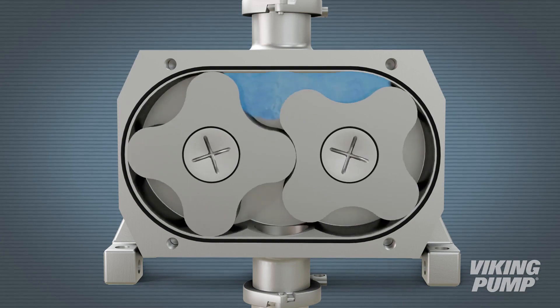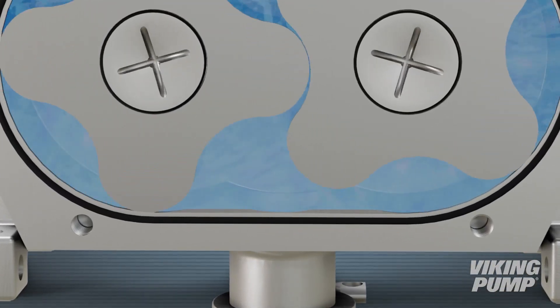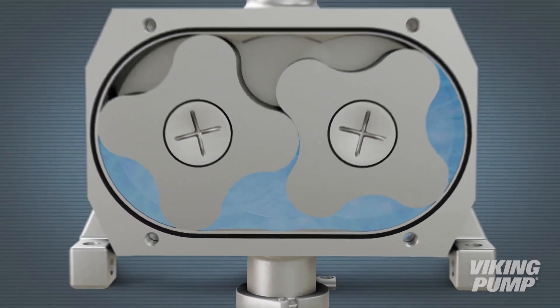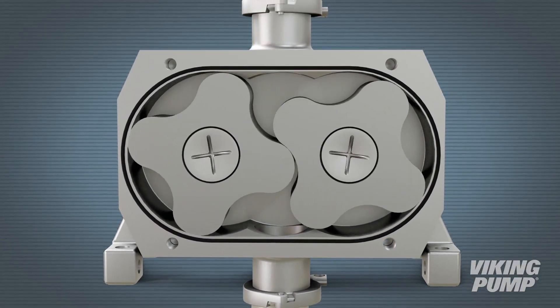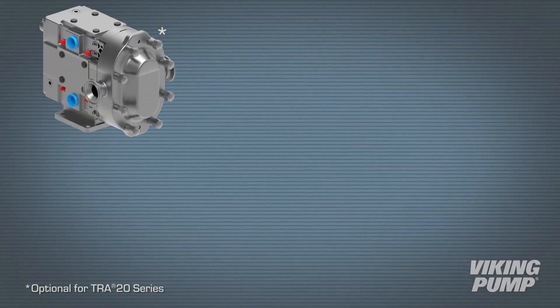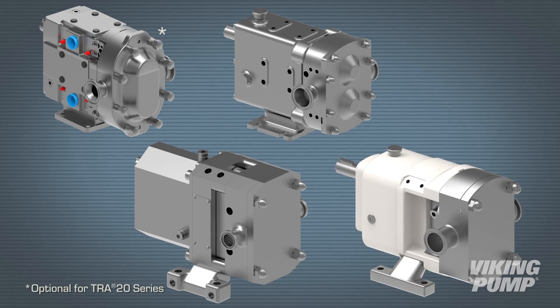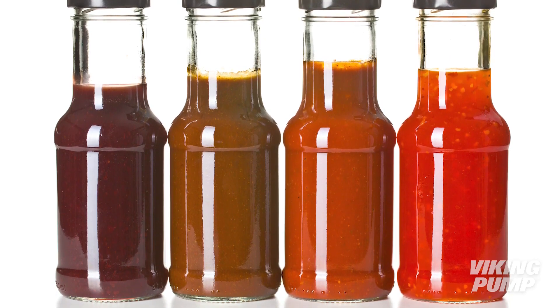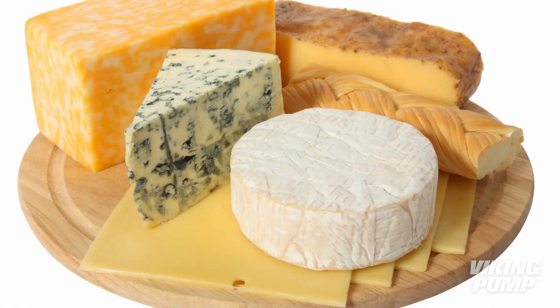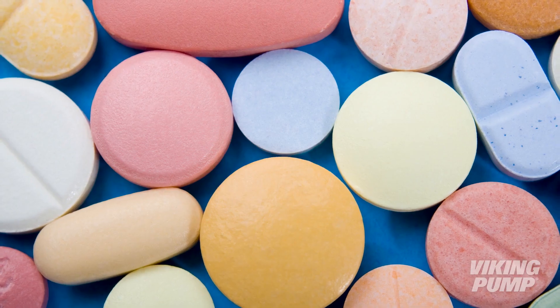CIP-able pumps are vertically ported and designed with special internal features to facilitate complete cleaning by CIP. The ability to completely self-drain is required for certifications like 3A or EHEDG. Viking CIP-able series include our TRA20, Revolution, Sterilobe, and the Classic Plus or Multipump series. Common Viking pump applications where CIP is used include foods with strong flavors, foods that contain bacteria like yogurt or cheese, and pharmaceutical processes.